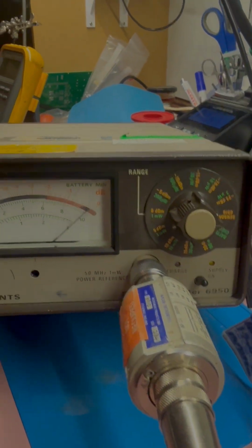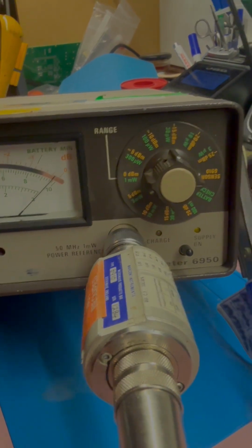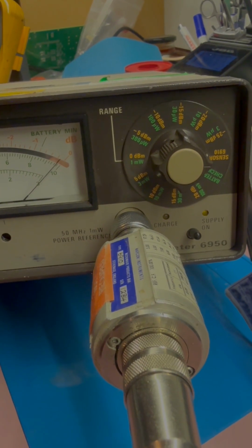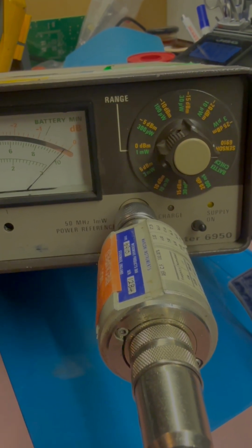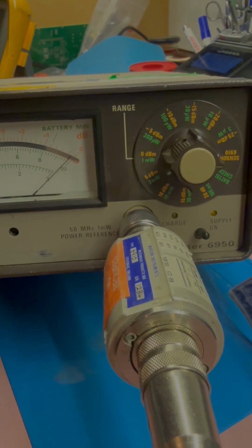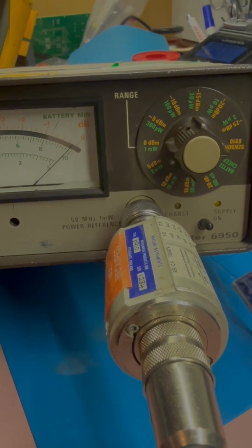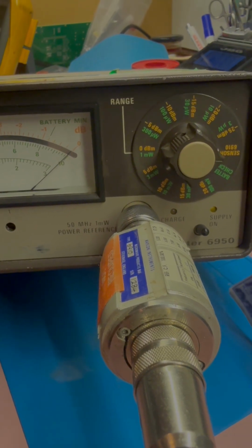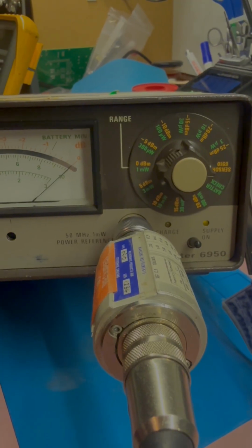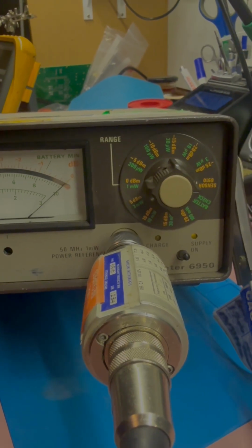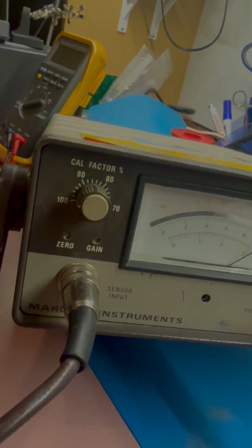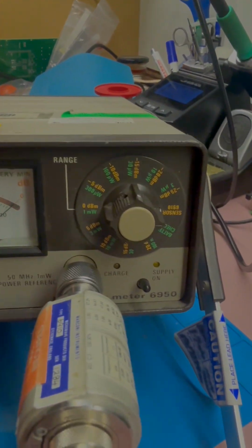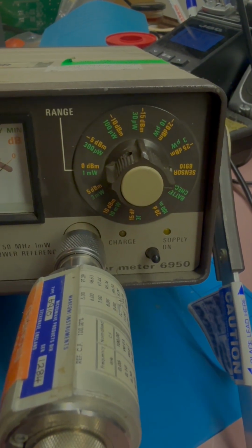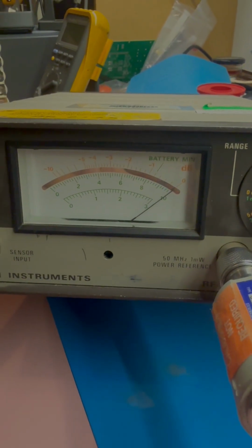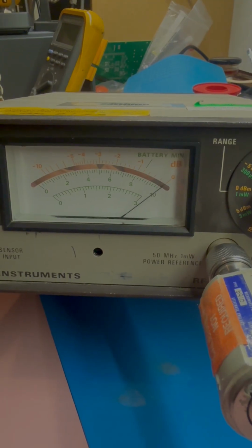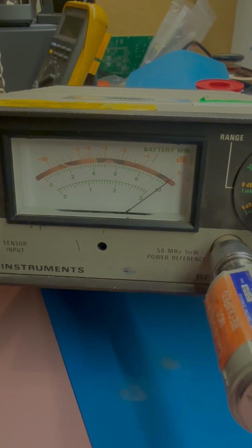We've now got the sensor connected to the internal source power reference, and we've got it switched on. There is a gain adjustment here, which I just need to put up ever so slightly. There we go, that's close enough for government work. The calibration is set to 100 as it should be on the 50 meg power reference, and the range is set to 0 dB. So we've now got the instrument calibrated. I'll now get the frequency generator out and we'll hook that up.